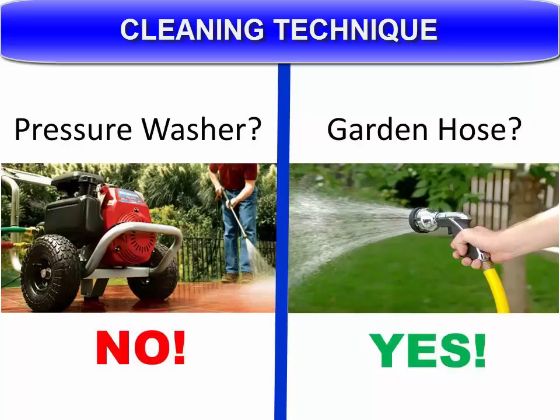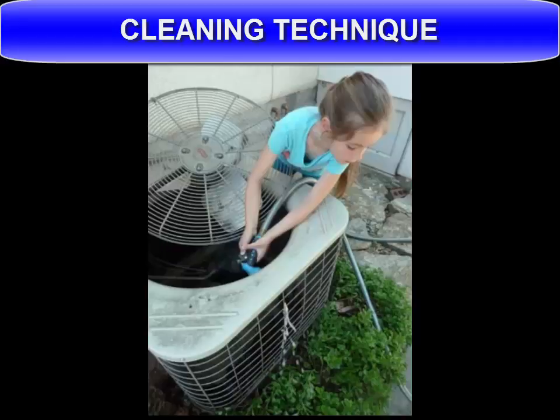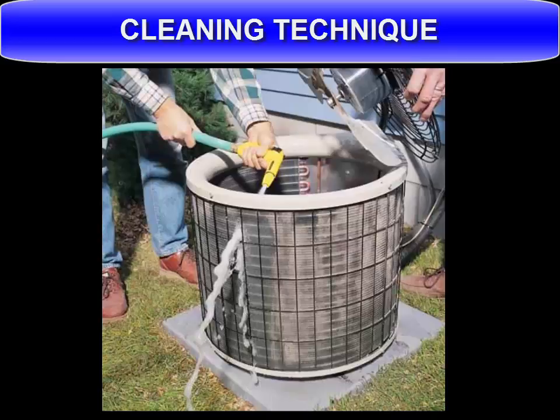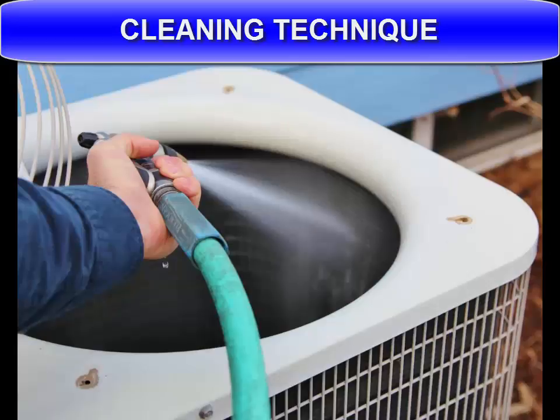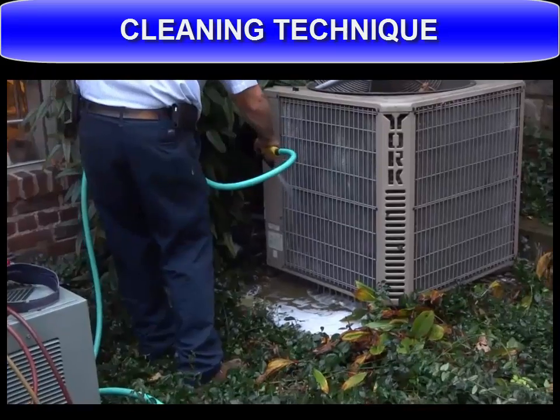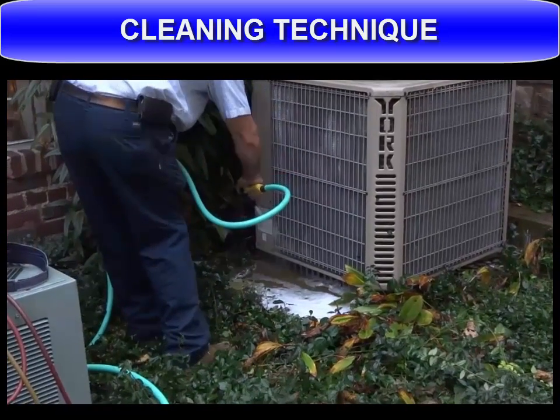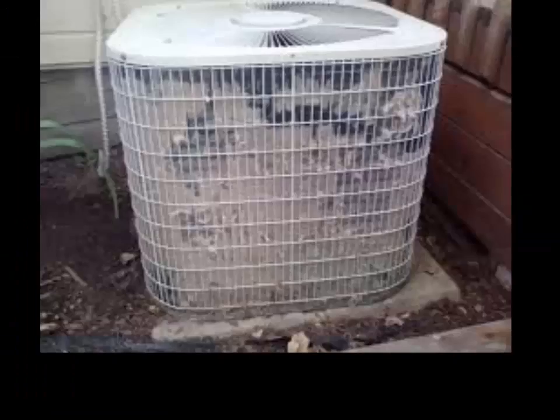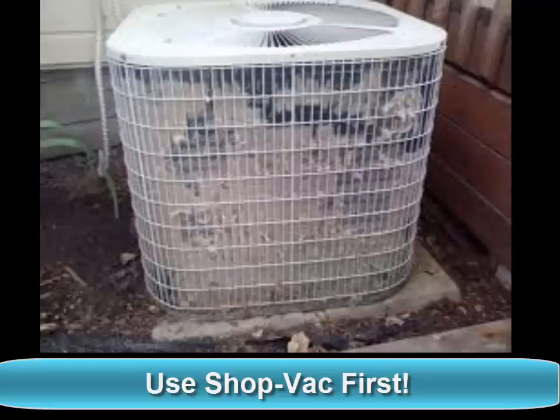Technique matters. Whether you're using a coil cleaner or not, you'll need a water source. Never use a pressure washer. Doing so could damage the coil fins and disperse chemicals into unwanted areas. Instead, use a standard garden hose. Begin by spraying the water from the inside of the unit outward, rather than from the outside inward, to prevent pushing debris further into the unit. Once you are certain all the debris has been dislodged, you can do final rinsing in all directions. In cases where there might be a thick film of dust, pollen, and grass clippings around the unit, a shop vac can be used to remove such debris before washing the coils.